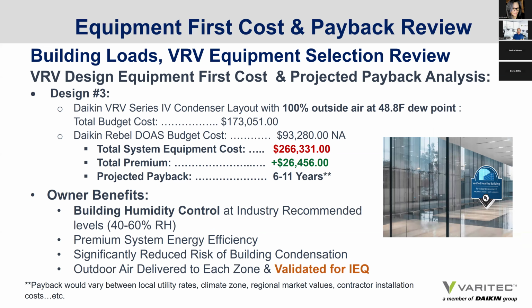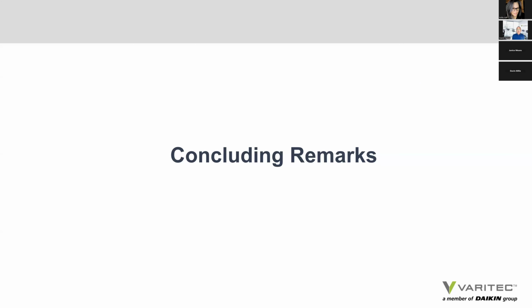Well, let's look at design scenario number three. Now the equipment cost does go up a bit because of the larger DOAS unit to achieve 52 degrees at the coil. So your total premium is $26,000 at 6 to 11 years projected payback, depending on actual building usage. But now you can really control your building humidity level to where it needs to be. During monsoon, it needs to be 40 to 60%, and you can control that humidity level. You offer premium system efficiency to your variable refrigerant system. You significantly reduce the risk of building condensation, and outdoor air is delivered exactly to each zone and can be validated and monitored for enhanced indoor environmental quality.